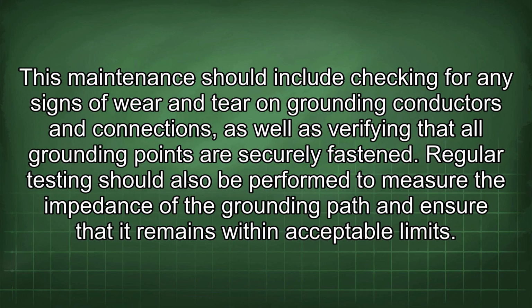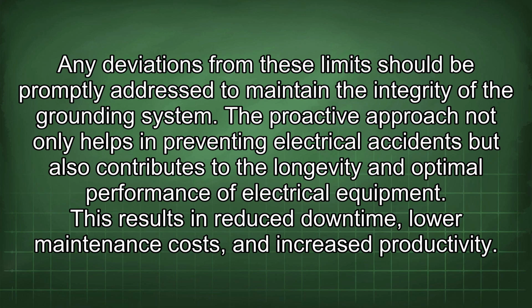This maintenance should include checking for any signs of wear and tear on grounding conductors and connections, as well as verifying that all grounding points are securely fastened. Regular testing should also be performed to measure the impedance of the grounding path and ensure that it remains within acceptable limits. Any deviations from these limits should be promptly addressed to maintain the integrity of the grounding system. The proactive approach not only helps in preventing electrical accidents but also contributes to the longevity and optimal performance of electrical equipment. This results in reduced downtime, lower maintenance costs, and increased productivity.